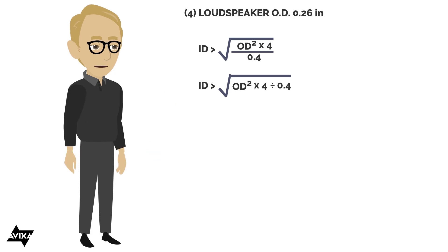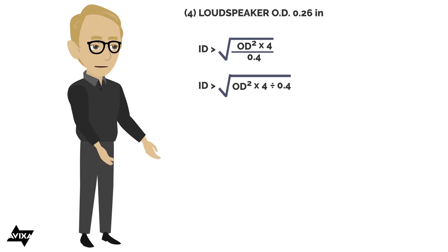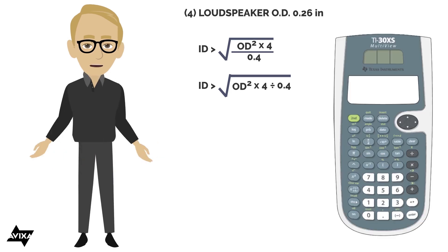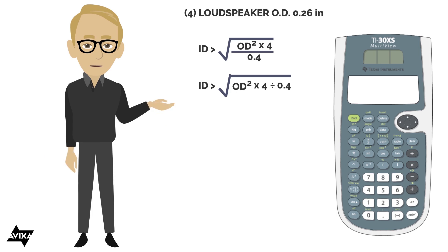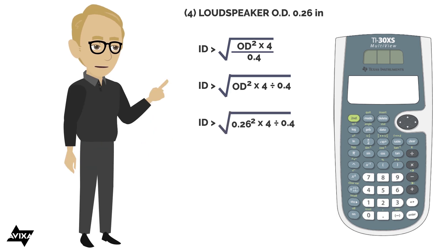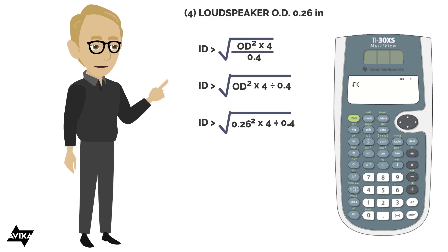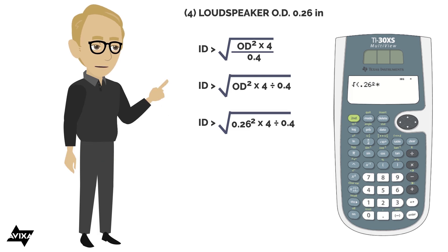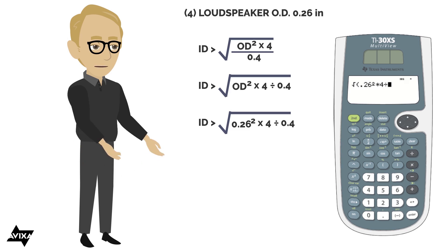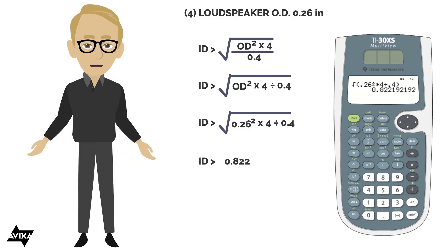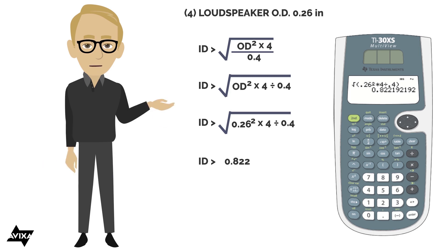Let's look at this in the light of PEMDAS. Outer diameter squared — it does the exponent first. This is all multiplication and division, so it follows left to right. I need to make sure everything is completed before I take the square root. So the entry is: square root of (0.26 squared times 4 divided by 0.4). Opening the square root function, entering 0.26, squaring it, multiplying by 4, dividing by 0.4, and closing the parenthesis. This tells me I need a conduit with an inner diameter larger than 0.822.